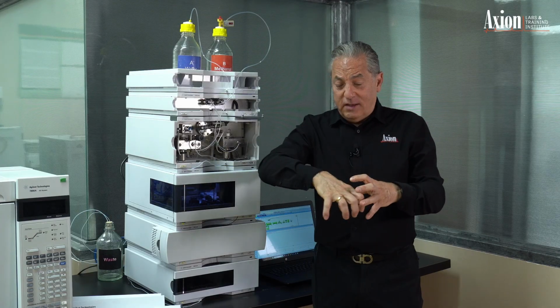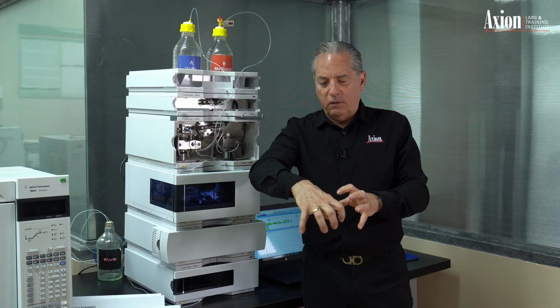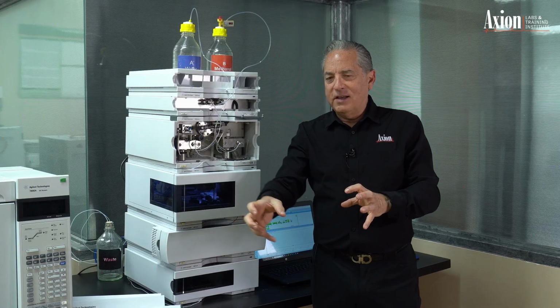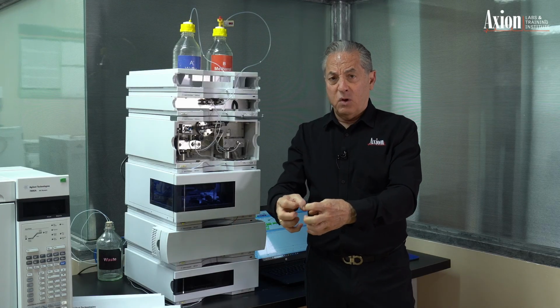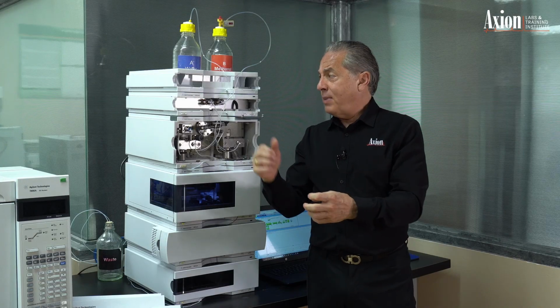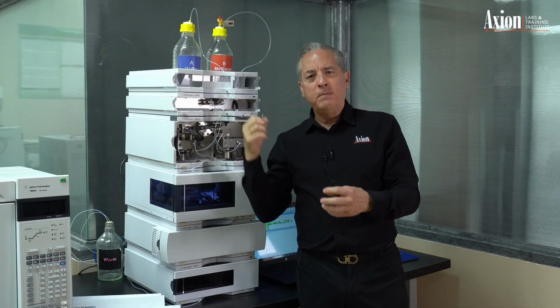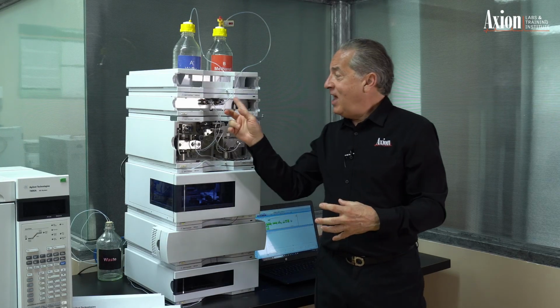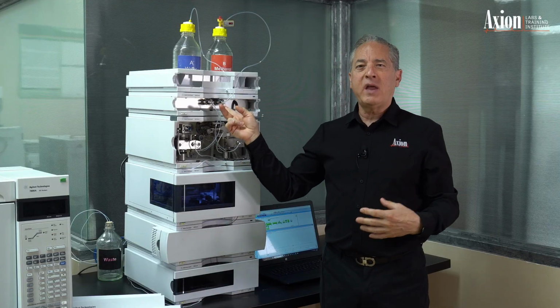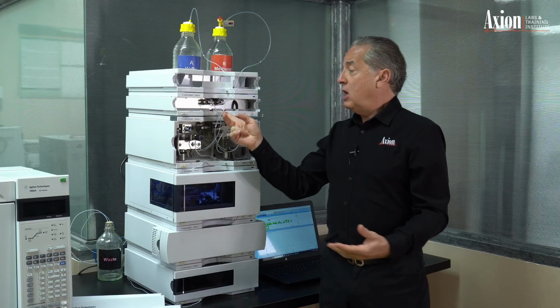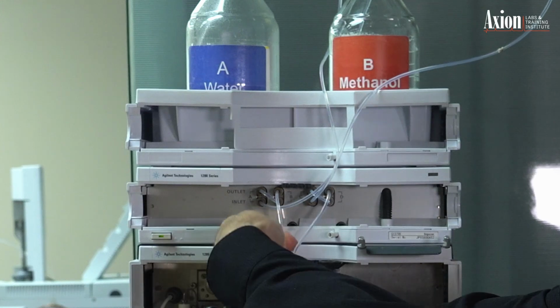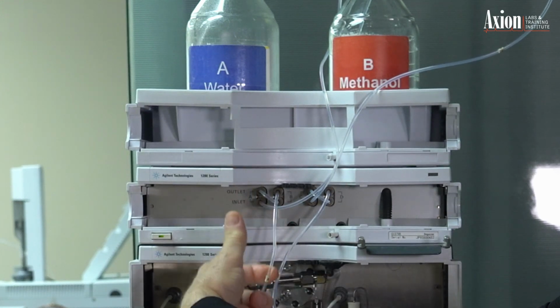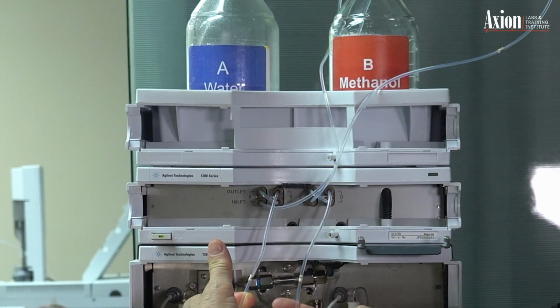So by the end of this long piece of tubing, these tiny little tubules, all the dissolved gases have been removed. They've come out as bubbles. They get pumped out. You can hear a little vacuum pump in here. At the end of this piece of tubing, coming out of the degasser, we have pure degassed mobile phase. Coming out of one side, the A channel, I have pure water. The B channel, I have pure methanol.